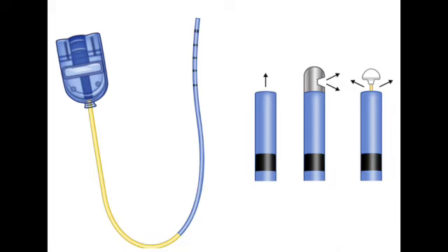Simple check. Okay, so we have the gas, the electricity, the right catheter, the grounding pad. But the real control and maybe the risk comes down to the settings on the machine. What are the key things the operator adjusts? There are basically 3 main knobs you're turning, so to speak. First is the electrical power, set in watts. Second is the argon gas flow rate, usually in liters per minute. And third, critically, is the duration, how long you actually press that activation pedal.